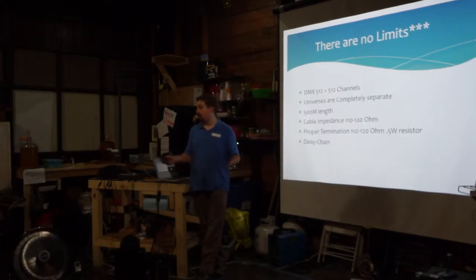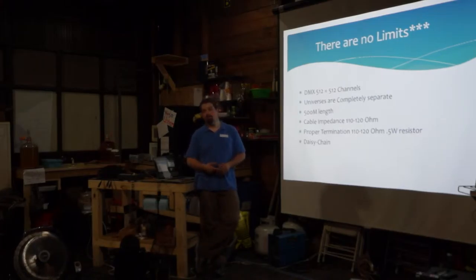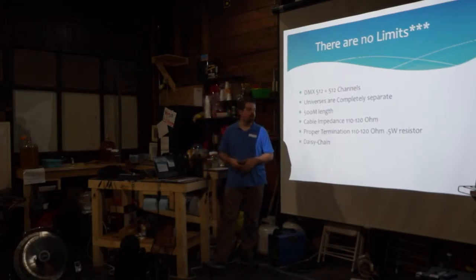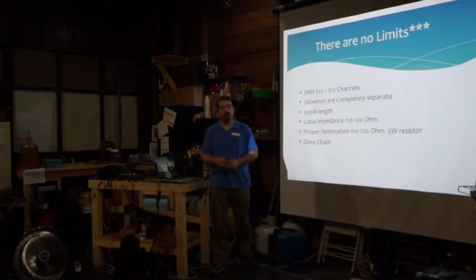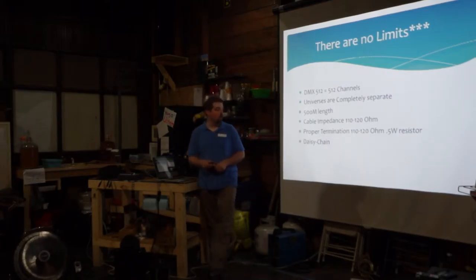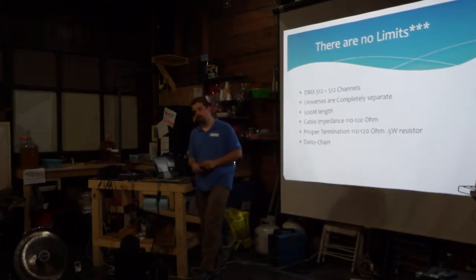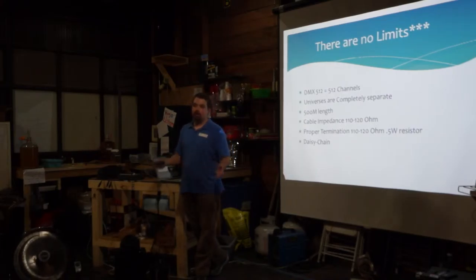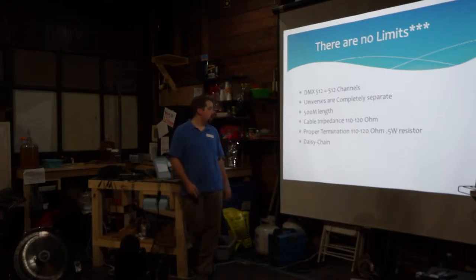500 meters is much longer than most runs. It's a daisy chain connection. Line impedance is around 110 to 120 ohms. At the end of a chain, the standard requires you to put a 110 to 120 ohm terminating resistor on the data lines. The reason you need that is to prevent signal reflection. On short lines, you don't have to worry about that. This is a daisy chain connection.